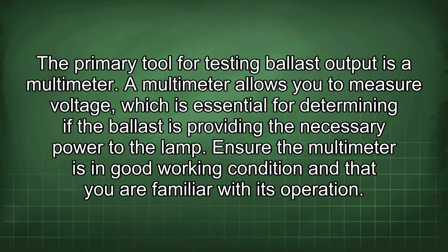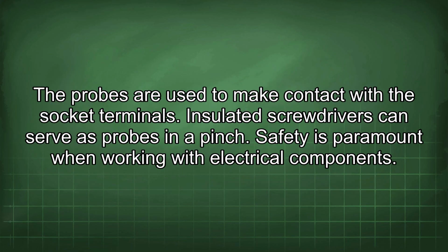The primary tool for testing ballast output is a multimeter. A multimeter allows you to measure voltage, which is essential for determining if the ballast is providing the necessary power to a lamp. Ensure the multimeter is in good working condition and that you are familiar with its operation. The probes are used to make contact with the socket terminals. Insulated screwdrivers can serve as probes in a pinch.